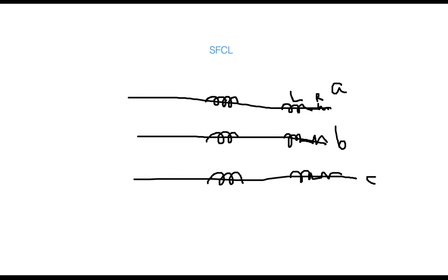Although this looks like an L, its inductance value is very small. In the actual line, the inductance value is much higher. But when I put in another coil, this does not mean it has a very high value. These inductors have a very small value. That's why these are called limiters. Instead of calling them inductors, they are called limiters because they will work during the fault current.